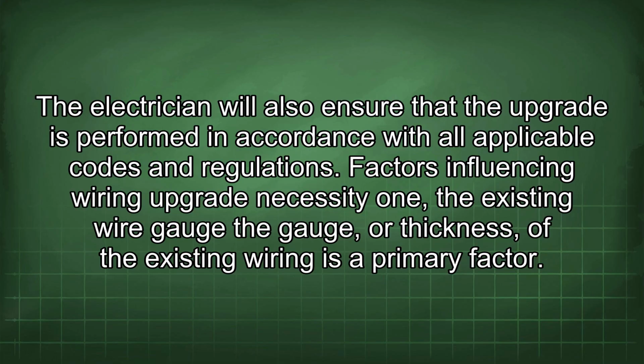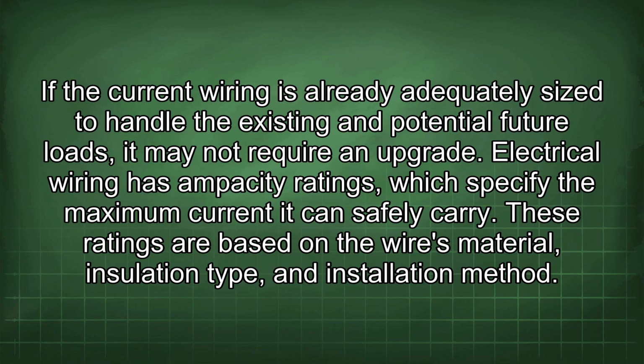Factors influencing wiring upgrade necessity: 1. The existing wire gauge. The gauge, or thickness, of the existing wiring is a primary factor. If the current wiring is already adequately sized to handle the existing and potential future loads, it may not require an upgrade. Electrical wiring has ampacity ratings, which specify the maximum current it can safely carry. These ratings are based on the wire's material, insulation type, and installation method.